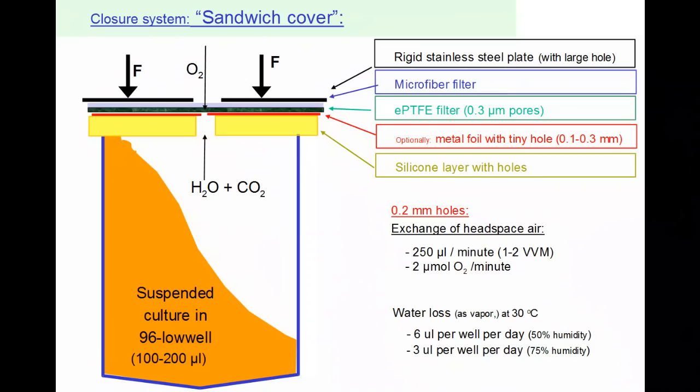The last component is a silicone layer with small holes above the center of each well. The main purpose of the silicone layer is to prevent cross-contamination and to limit evaporation. The size of the hole determines the supply rate of fresh air to the culture and also the evaporation rate.